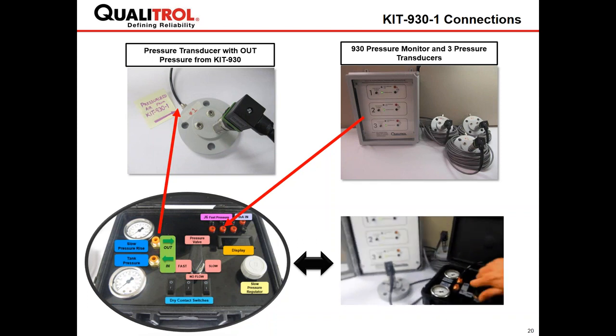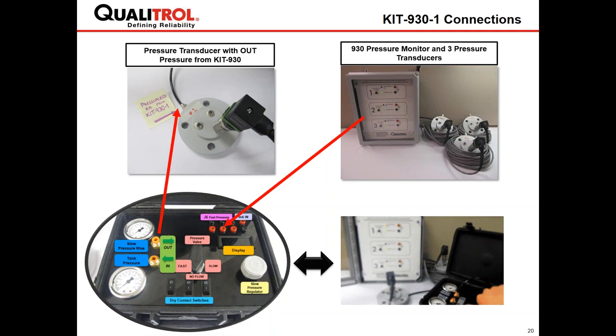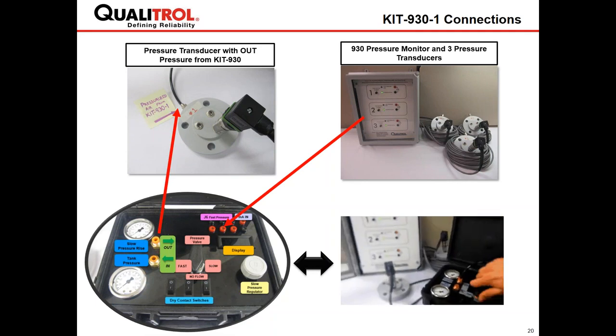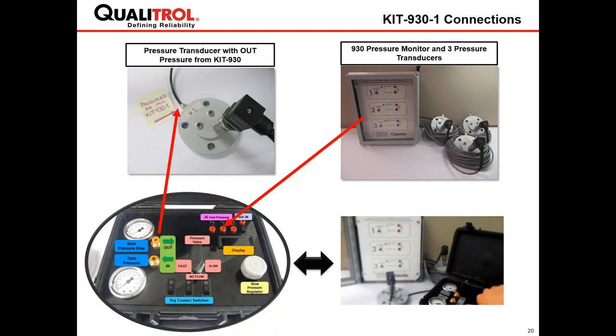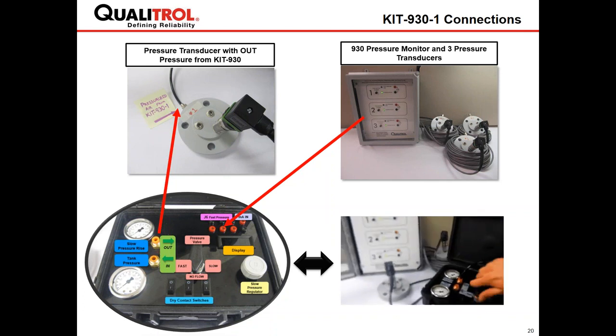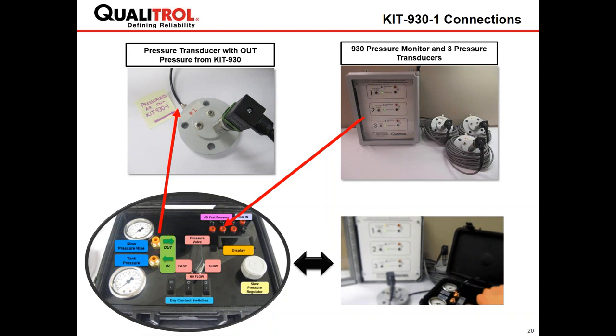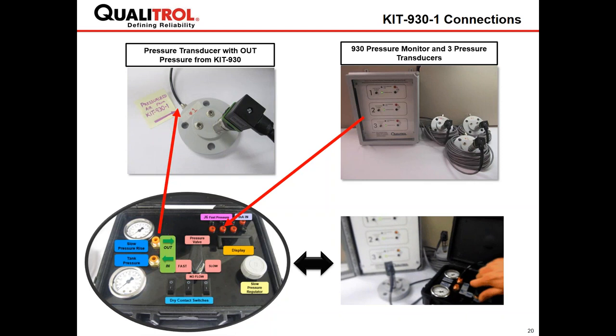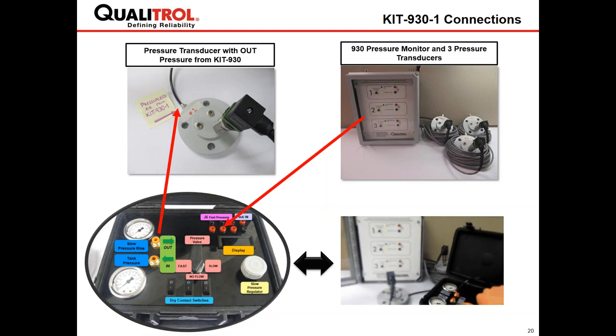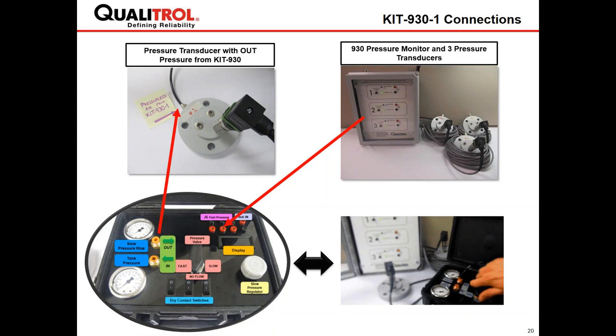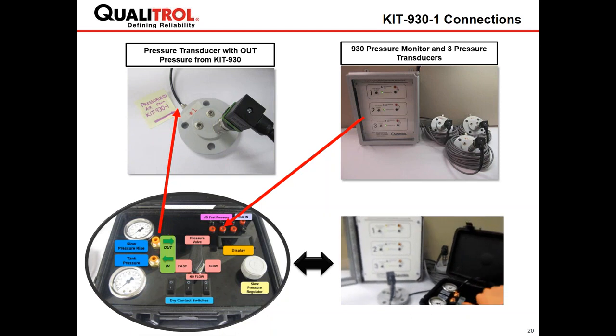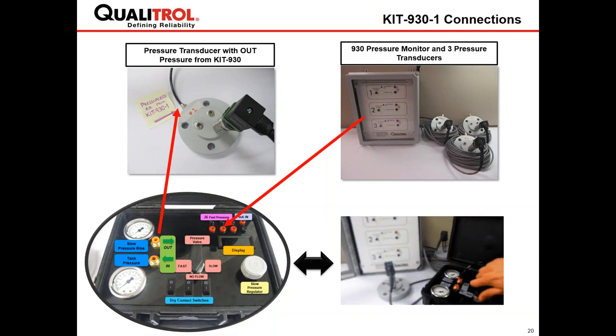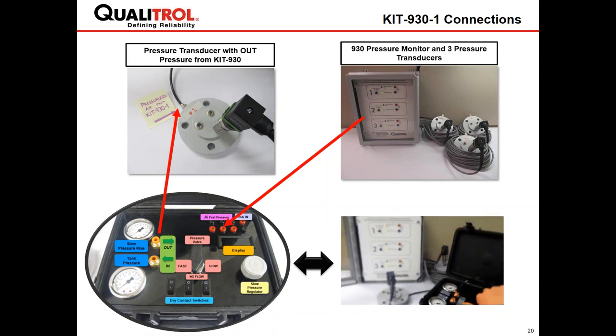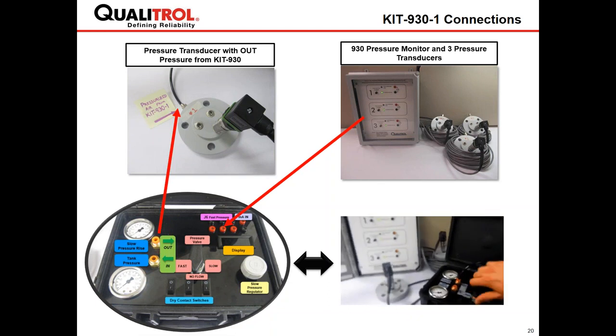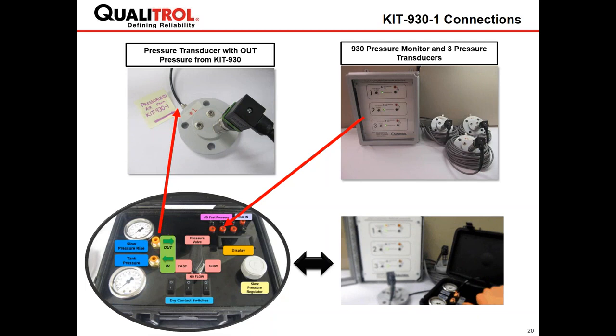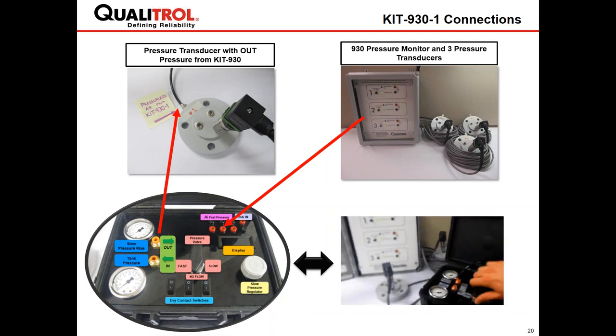On the right-hand side, you have an example. This is a 930 monitor. It is a three pressure transducer configuration. In some cases, we have customers that utilize one flange with 3 pressure transducers right on it. That's when a customer would like to look at pressure at the same location. What you see in front of your screen, we have 3 different flanges and 3 different pressure transducers, meaning in this case, the customer would like to look at pressure at 3 different locations. From the monitor to the kit, you can connect the milliamp output right on here and also check for the dry contact test that will be performed in the next slide.